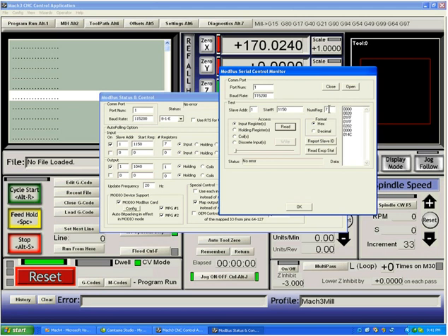Each address in a ModBus is 16 bits. After opening the port, we can read the data, and you can see this is the data coming from Peter's board at the moment. The first word that's coming in is 0. This is a bit-packed word of his 8 bits of input data.